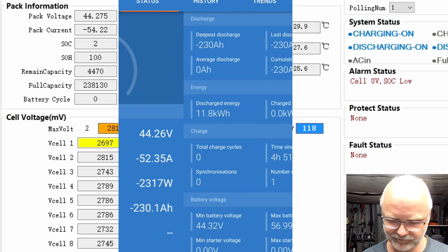Okay, 2.69 I can see here, and the highest voltage cell is 2.8. Look at this, 150 millivolt difference. Maximum 100 to 150 millivolt, depending where the BMS measures. Under 43 volts pack voltage, almost all the cells are yellow now. They are all under 2.7 volts.